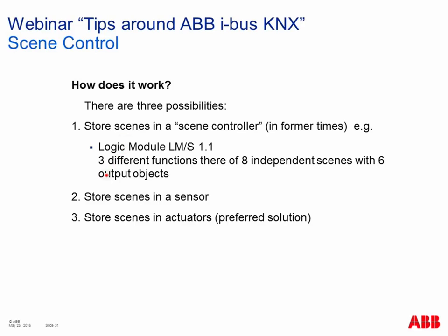And some years later, the manufacturers of the sensors integrated this scene function into the sensors. So today it is quite common to store the scenes in a sensor. And the manufacturers of the actuators have also integrated the scene function in the actuators. So today we have two possibilities: to use the scene function in a sensor or to use the scene function in actuators. Now I show you all these three possibilities, and I think the best solution, as you will see later, is to store all the scenes in the actuators.